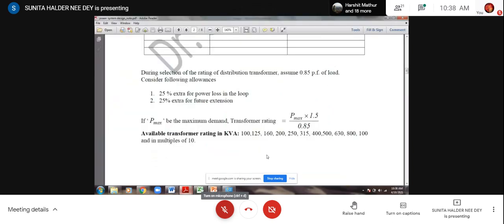So that is noted here. This is P max. This is 0.85. We are assuming that the transformer is lossless, so efficiency is not included here, though actually transformer efficiency is near 95%. So P max by 0.85 into 1.5. Why 1.5? Have you understood? 25% extra for power loss in the loop. Loop means there will be a closed loop ring main system, that is why it is called a loop. 25% extra for expansion. So you can calculate the transformer rating very easily.